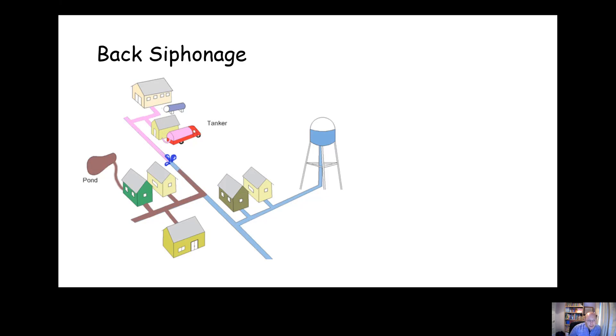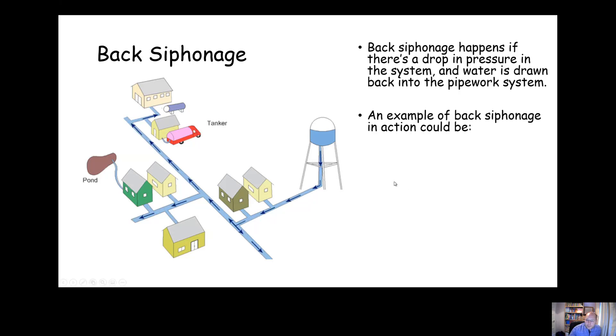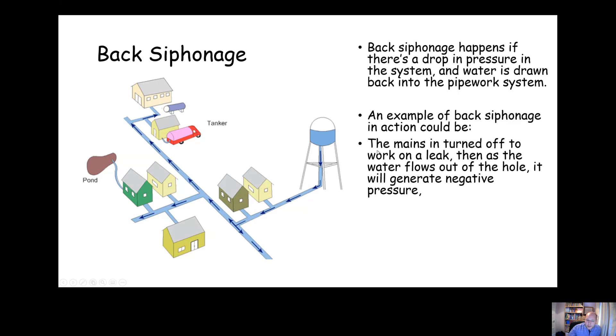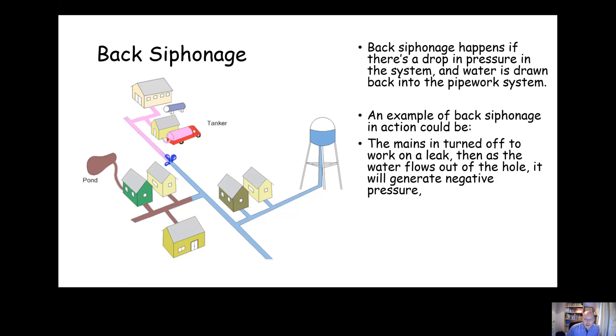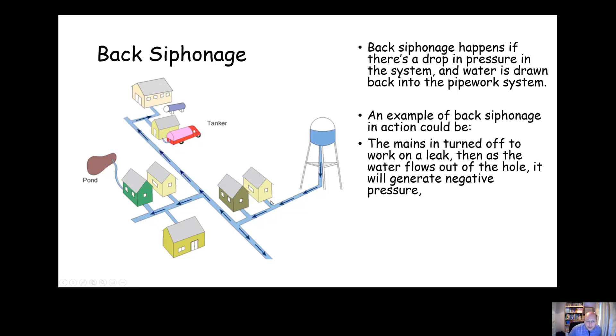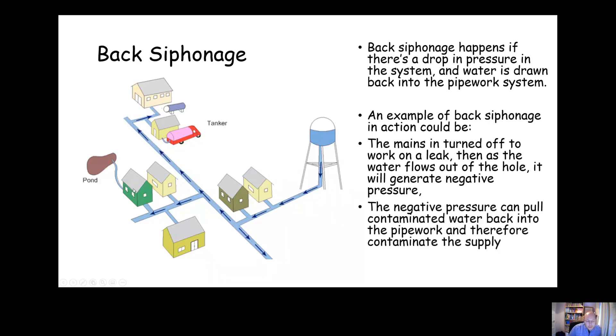Another example is back siphonage, which is probably the main issue. It can be caused by a drop in pressure downstream — for example, caused by a leak — which could then cause water to be drawn back into the system because of negative pressure, ending up with contaminated water being pulled into the mains and causing a risk to health. For example, if the mains is turned off to work on a leak, the water flowing out creates negative pressure which can pull contaminated water into the pipework and contaminate the supply.